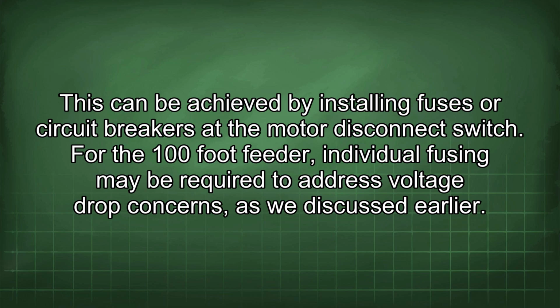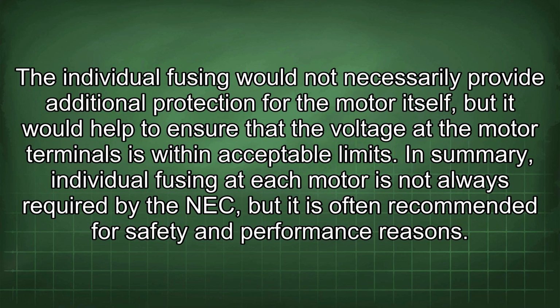For the 100-foot feeder, individual fusing may be required to address voltage drop concerns, as we discussed earlier. The individual fusing would not necessarily provide additional protection for the motor itself, but it would help to ensure that the voltage at the motor terminals is within acceptable limits.